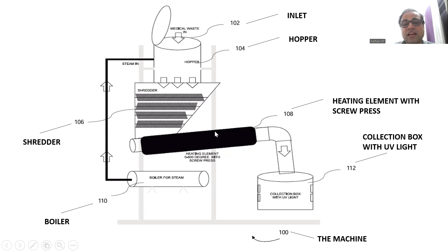And then we come to the final step, where the method comprises draining and screw pressing excess liquid present in the shredded medical waste. Which means that after the shredding of the medical waste is complete, the shredded medical waste is administered to a screw press. This press is more like a pressing device which drains out all the liquid that may be present in the medical waste, and along with that, it is also subjected to a little bit of heat so that any liquid content, any water molecules present in the medical waste, can get evaporated. So that is what happens at 108, which is the heating element with screw press.